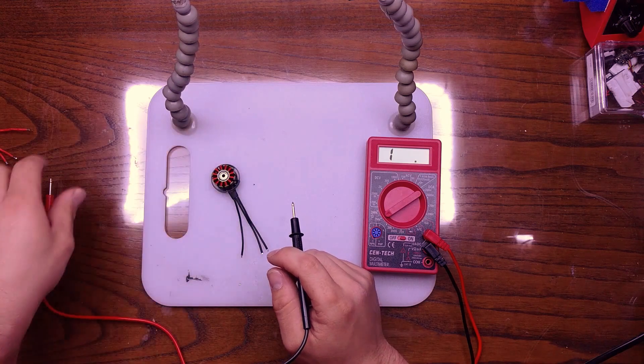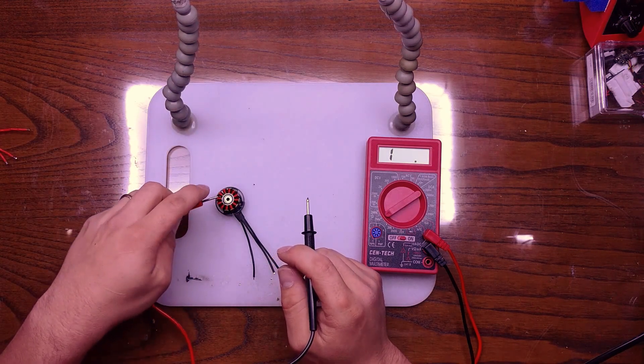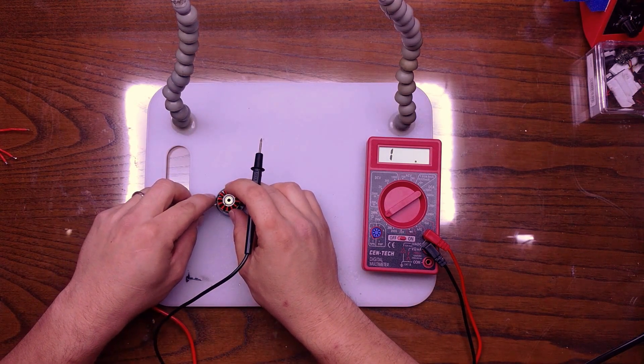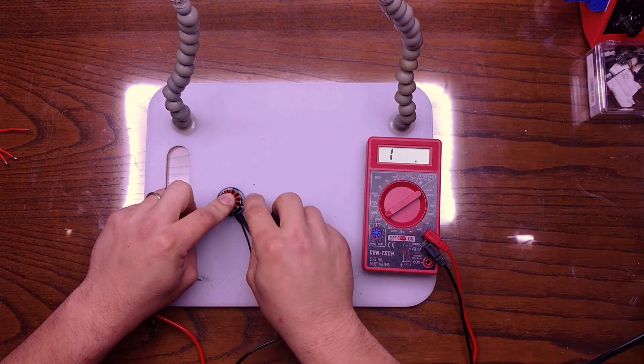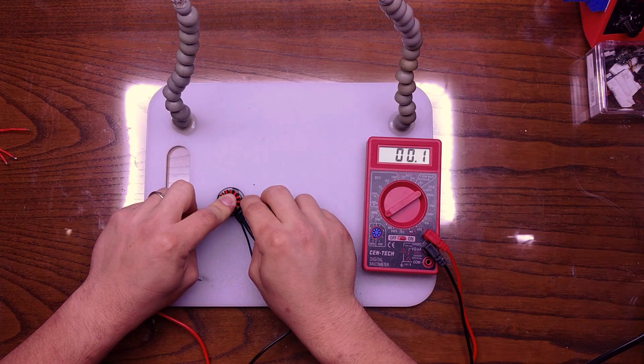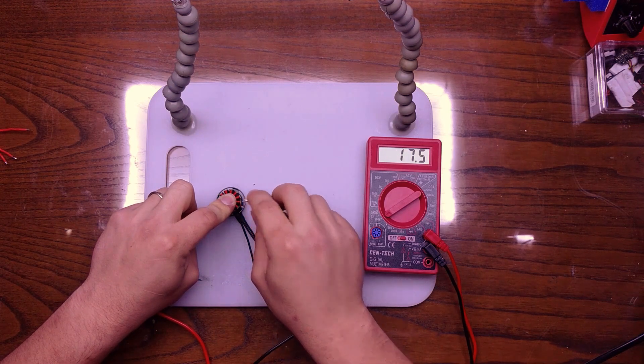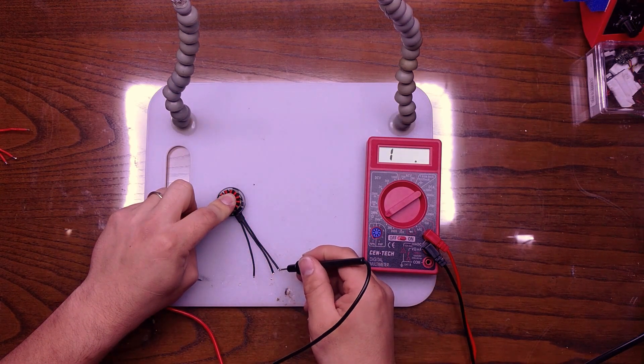This one is some new motors that I'm currently working on and I have already tested it. This one is a good one, but I'm going to go ahead for the sake of the video and show it again. So again, make sure that you have contact to your stator and then just come over here and touch one of the leads.